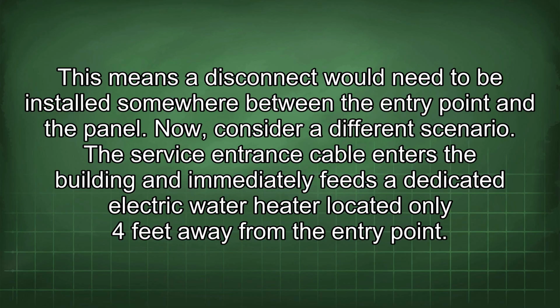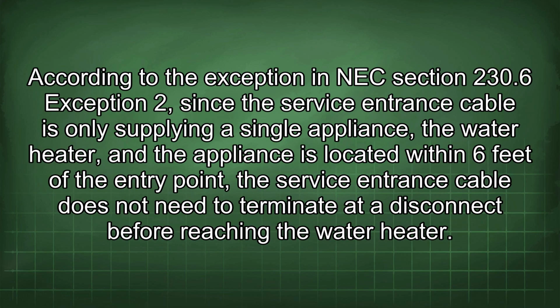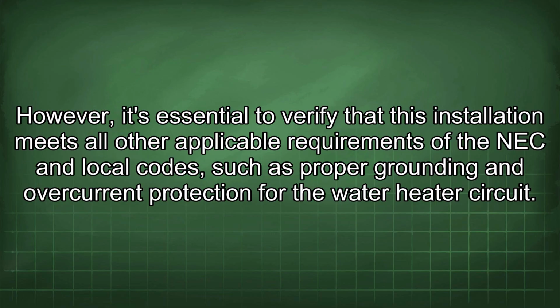Now consider a different scenario. The service entrance cable enters a building and immediately feeds a dedicated electric water heater located only 4 feet away from the entry point. According to the exception in NEC section 230.6 exception 2, since the service entrance cable is only supplying a single appliance, the water heater, and the appliance is located within 6 feet of the entry point, the service entrance cable does not need to terminate at a disconnect before reaching the water heater. However, it's essential to verify that this installation meets all other applicable requirements of the NEC and local codes, such as proper grounding and overcurrent protection for the water heater circuit.